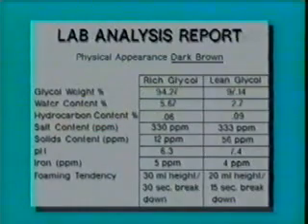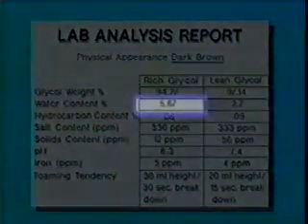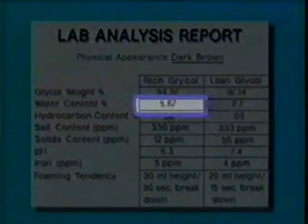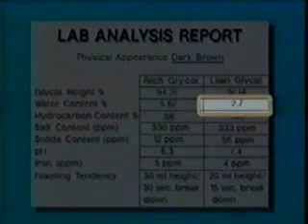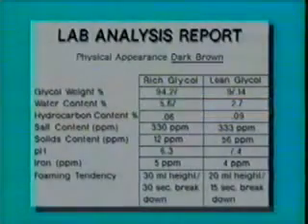Let's take a look at our sample. The water content for the rich glycol is acceptable. However, the lean glycol water content is too high. Again, this means that some adjustments may need to be made.